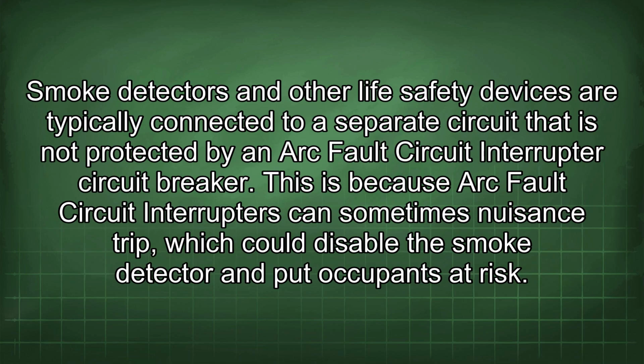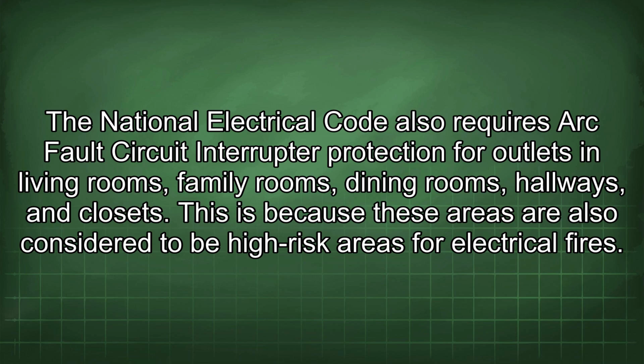Smoke detectors and other life safety devices are typically connected to a separate circuit that is not protected by an arc fault circuit interrupter circuit breaker. This is because arc fault circuit interrupters can sometimes nuisance trip, which could disable the smoke detector and put occupants at risk. The National Electrical Code also requires arc fault circuit interrupter protection for outlets in living rooms, family rooms, dining rooms, hallways, and closets. This is because these areas are also considered to be high-risk areas for electrical fires.